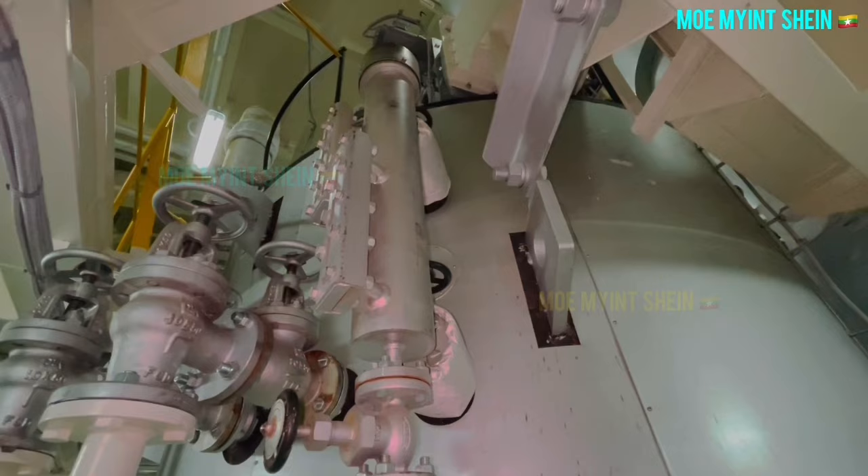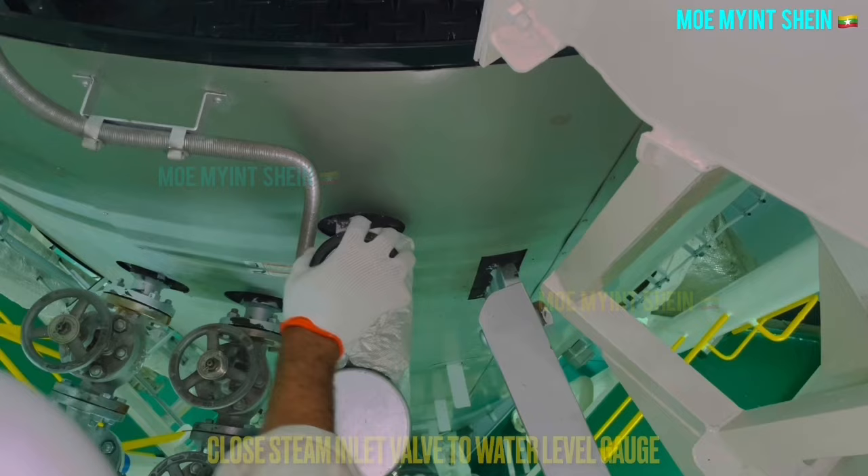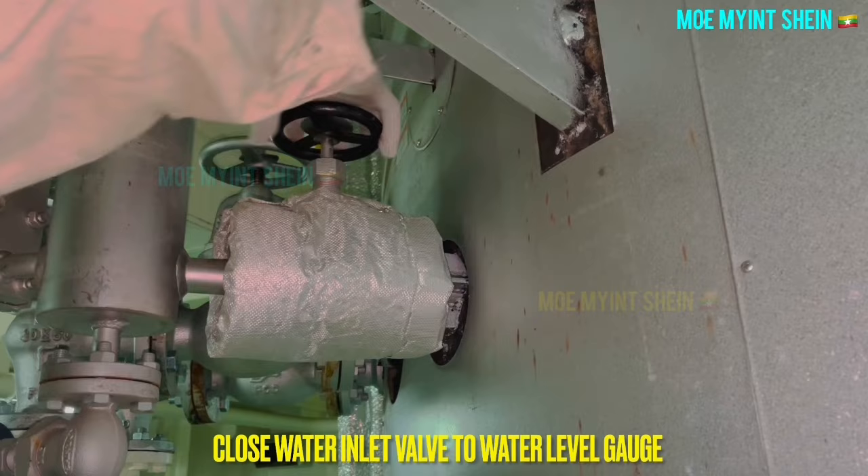A water level gauge with the level sensor is fitted in this boiler. Okay, let's test. At first, close the steam stop valve to the water level gauge, then close the water stop valve. Slightly open the drain valve and gradually drain water inside the level gauge.